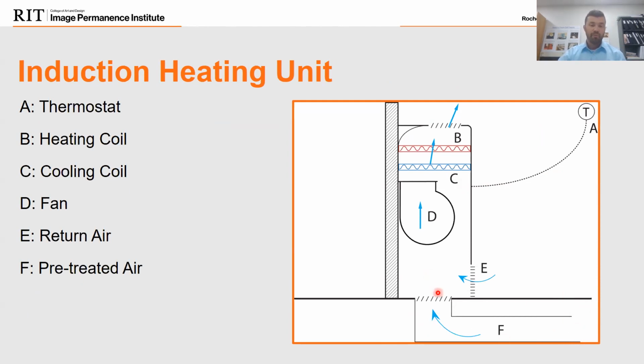So they may have some form of pre-treated air, but the air in the room will be exhausted, come back out in this circle, be brought in through the vents somewhere, most likely on the bottom. The fan will pull the air through, push it out, and you'll either heat or cool. This will likely not do both. It will either cool the air sensibly or heat the air sensibly, and then reject the air back out into the room. So again, this is that sensible condition I was talking about. We're not doing any moisture removal. Any moisture removal with this type of unit is just happenstance. So we're just going to do that sensible condition change and then just keep this moving in this circle, if you will.